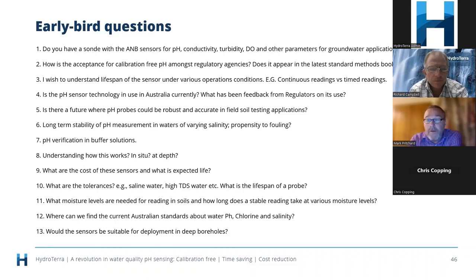Well, we're running on RS-232/485—RS-232 comms is about 20 meters, and 485 direct cable attachment is about 150 meters. Then if you go into data repeaters, IoT networking the units, putting on telemetry systems, there's really no limit to the distance of operation. The units are ideal for remote operation because of the nature of the beast—we need a 5 to 42 volt DC input, and with that we charge the chemical pellet. It's electromechanical operation, and we then read the peak from those pellets to denote the pH and the salinity.